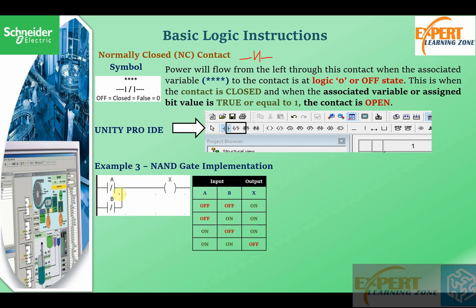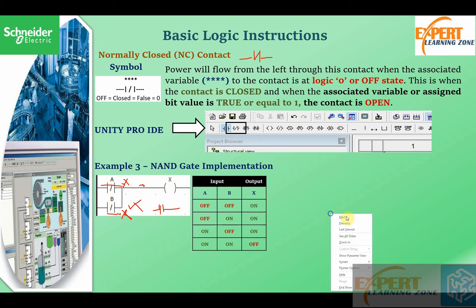We can use normally closed contacts to implement the NAND operation. The NAND operation says that when both inputs are one the output is zero. When A is off and B is off, logic flows through both closed contacts to the output. When one of them is on, that contact prevents the flow of logic. When both are on, they both open and prevent the flow of logic, so the output becomes off.